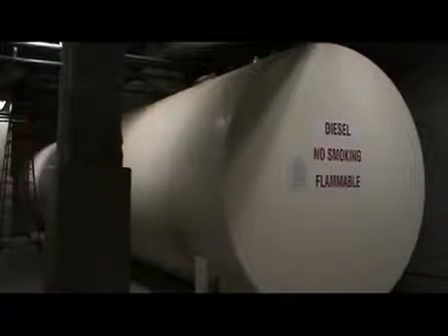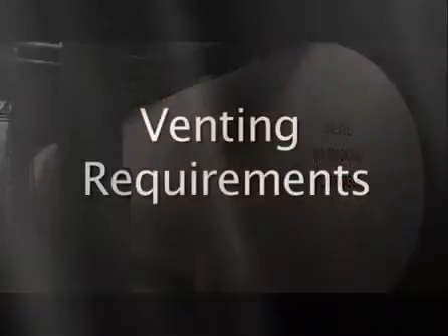Tanks in buildings are typically steel horizontal tanks with integral supports. Rectangular tanks are often used because they have a smaller footprint for a given tank capacity. Tanks need to be contained by either double wall construction or room construction that provides for diking. While tanks are sometimes fire-rated construction, the fire protection is often provided by the room construction itself, allowing for the use of a standard steel tank.